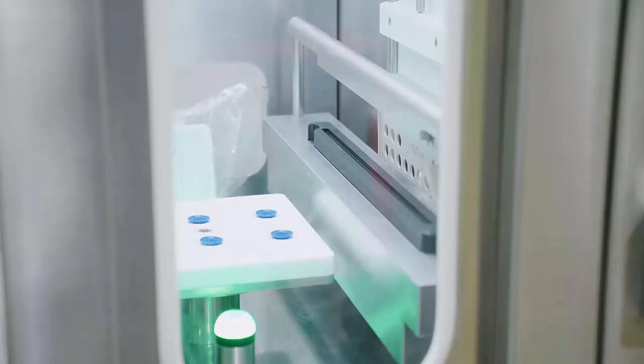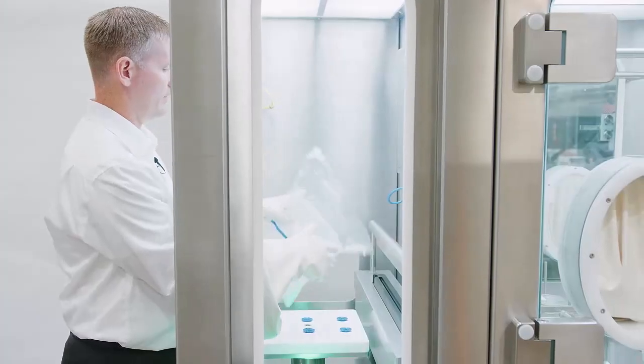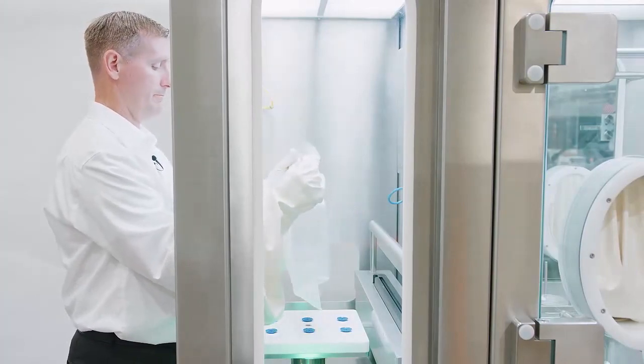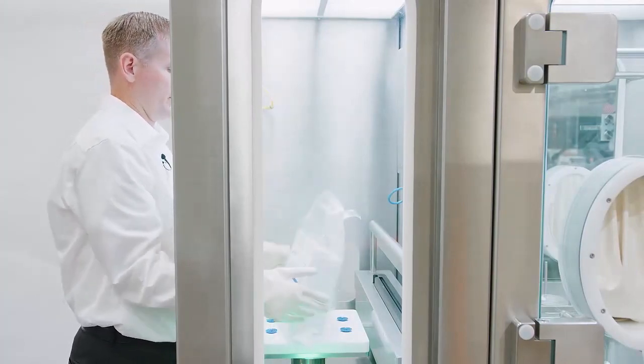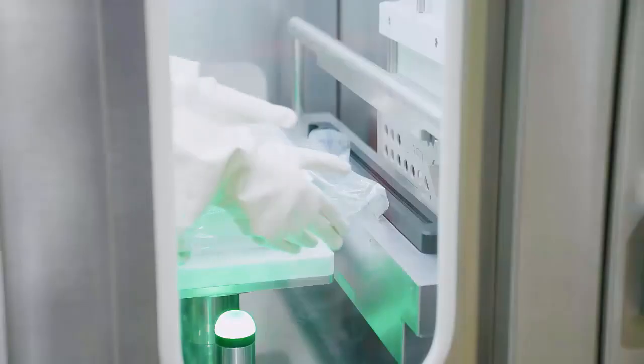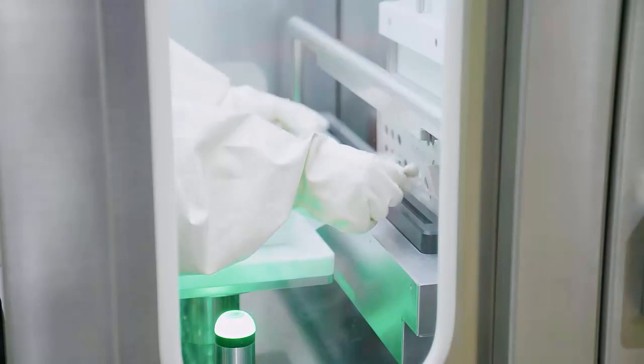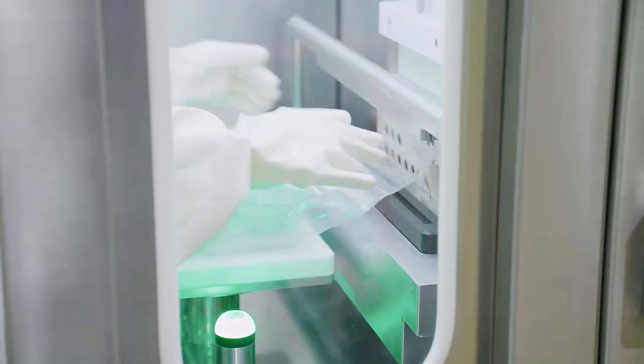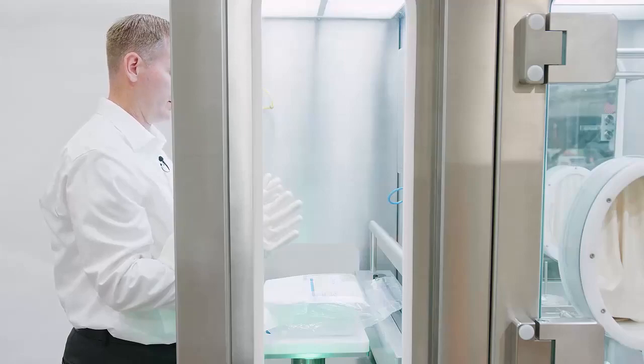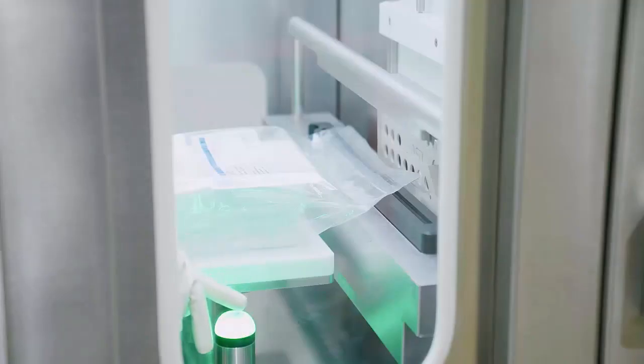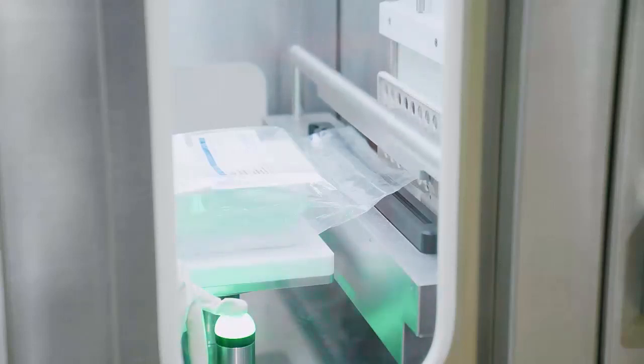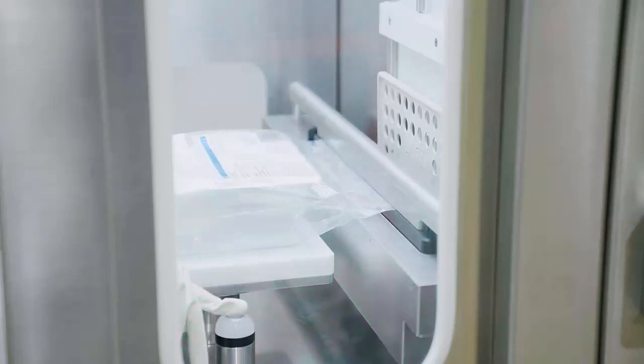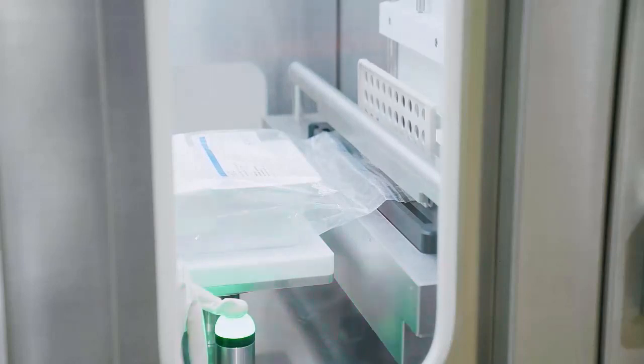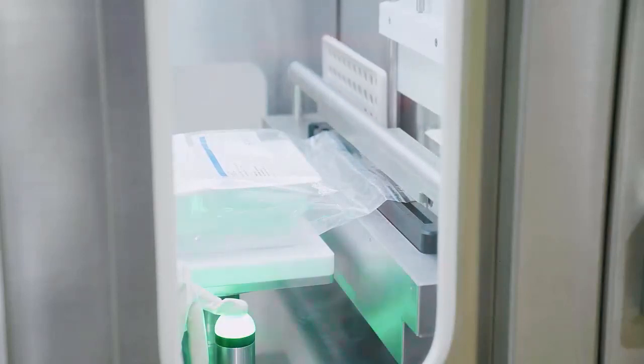The operator uses the glove ports to bring in a roller conveyor that feeds the vials with the overbag placed on it. They place it on this table and on the cutting head assembly via the glove ports. Once the bag and tub are properly placed, they put their fingers on the safety switches to ensure their gloved hands are clear of the operating equipment. If they remove their fingers, the system stops. Otherwise, the system performs the cut, and the door and mouse hole to the aseptic isolator now open.